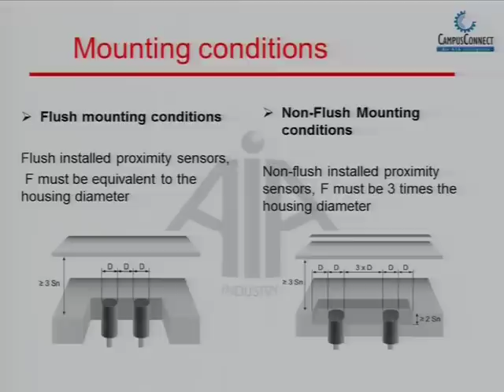So, there are two types. If you are using a flush type of sensor, the distance between the two sensors should be 1 times the diameter. That means if 18 mm is the sensor diameter, there should be a gap of minimum 18 mm and then the second sensor can be mounted. If we are using a non-flush sensor, then 3 times the diameter is the distance between the two sensors. Below that we cannot use it, right, because they will interfere with each other.